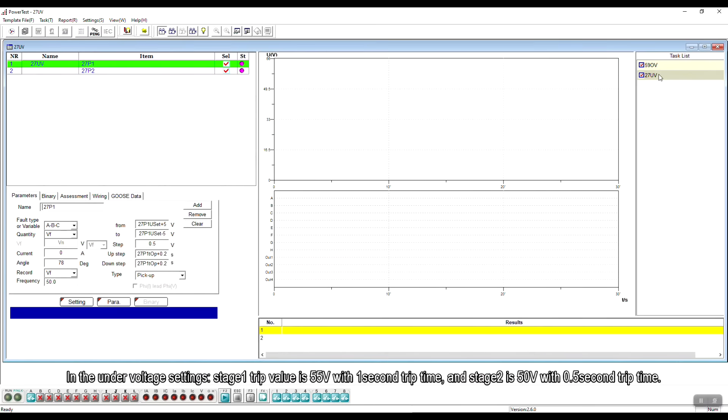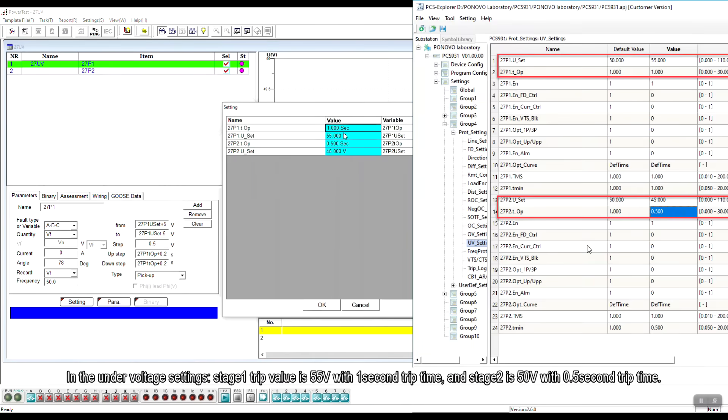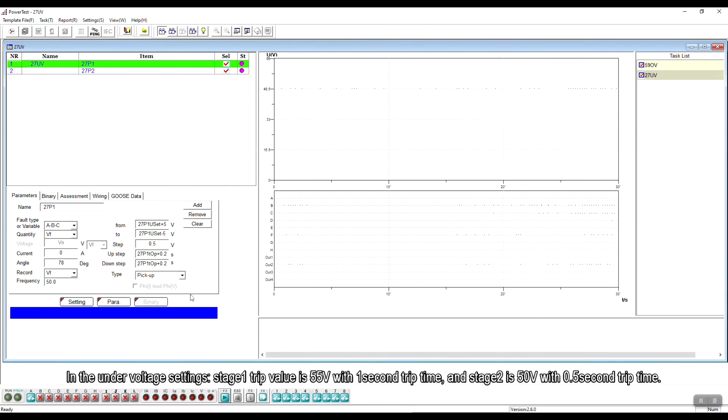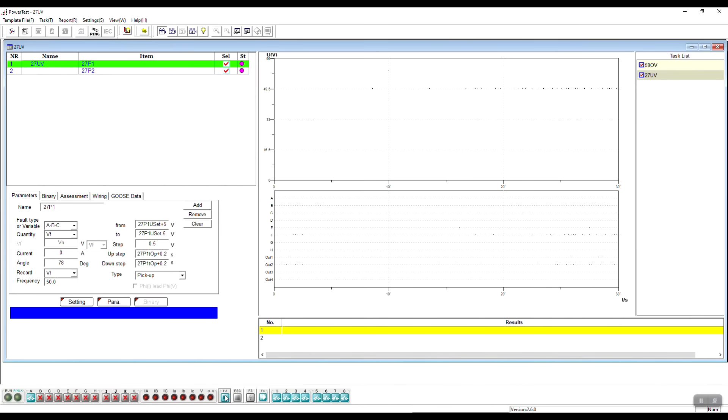In the under-voltage settings, stage 1 trip value is 55V with 1s trip time and stage 2 is 50V with 0.5s trip time.